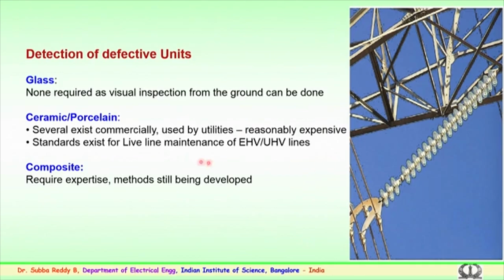For ceramic or porcelain insulators, several commercial methods are available which are normally employed by the utilities and the power grid engineers. These are reasonably expensive, and standards also exist for live line maintenance and measurement of field to find out whether the insulators are faulty or good. For composite insulators it requires a lot of expertise, as mentioned, these are of recent origin.